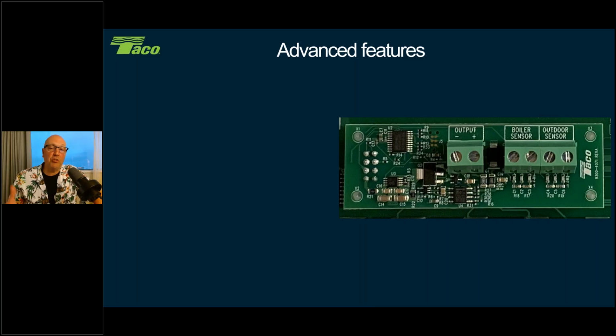So here's the close-up of that board, and you'll see a couple of terminals on here. You'll see the output terminal, plus minus. We have boiler sensor and outdoor sensor. So when you order the PC800 to add to one of those boards, it will come with one strap-on temperature sensor, which is meant for your boiler supply. So the boiler sensor is your boiler supply. If you want to do outdoor reset, you still need the boiler supply sensor that comes with the card, but then you will need to get an outdoor sensor that you will plug into the outdoor terminal here.